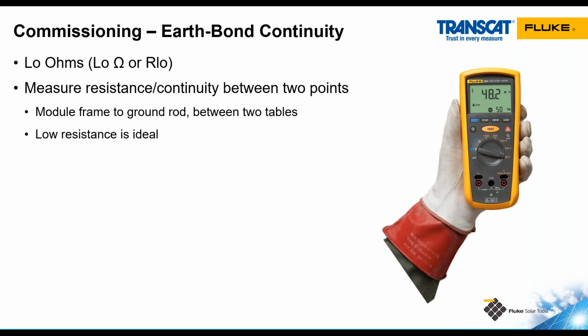Another test we do at commissioning is earth bond continuity testing. This is a measurement of resistance in ohms. We're checking the continuity between 2 points, and that could be any 2 non-current carrying metal parts like the module frame to the racking, between different racking sections or tables. It could be between the module and the ground rod. Any 2 metal points, we can test resistance.